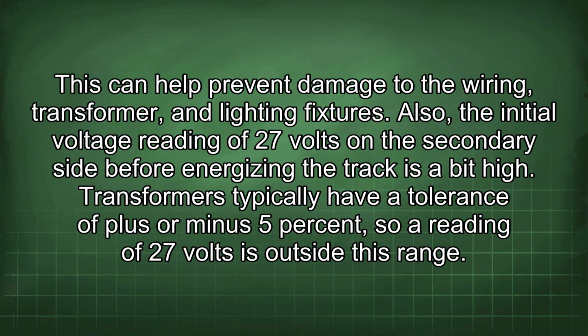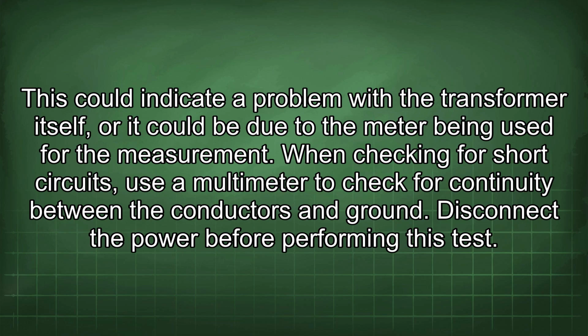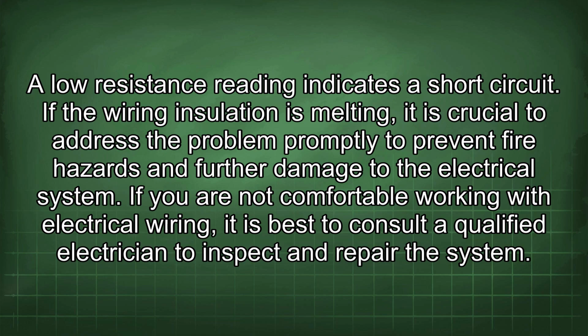Also, the initial voltage reading of 27 volts on the secondary side before energizing the track is a bit high. Transformers typically have a tolerance of plus or minus 5%, so a reading of 27 volts is outside this range. This could indicate a problem with the transformer itself, or it could be due to the meter being used for the measurement. When checking for short circuits, use a multimeter to check for continuity between the conductors and ground. Disconnect the power before performing this test. A low resistance reading indicates a short circuit.